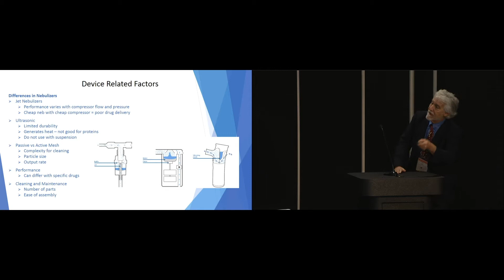So one option back in the 80s was the ultrasonic nebulizer that uses a piezo ceramic element. You have a piezo ceramic element, it vibrates, it puts vibration through the liquid, and it creates a standing wave in the medication cup, and those particles are what then goes on to the patient. It's pretty good technology.